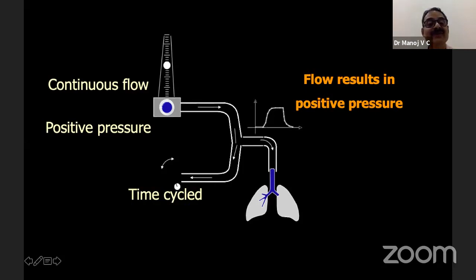So there is a valve here. When this valve is closed, the pressure here is very high, so the gas has to go to the lung. The moment the valve opens, it will flow out, and the air in the lungs also will come out until it equilibrates with the pressure that is generated here. That is what you are going to set as PEEP, positive end expiratory pressure. Until that point, the lung will keep exhaling, and all this will go out. Now, who determines when to open and when to close? That is your cycling mechanism. By default, all ventilators have a time cycling mechanism. And this pressure generated with this flow is what you try to use up.